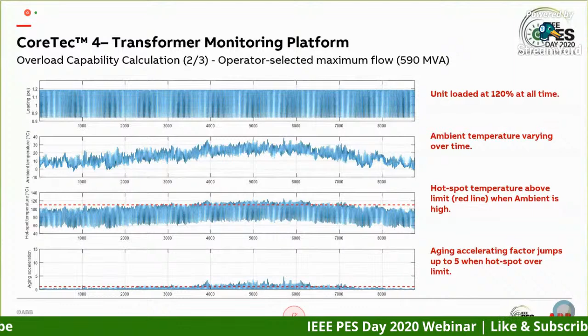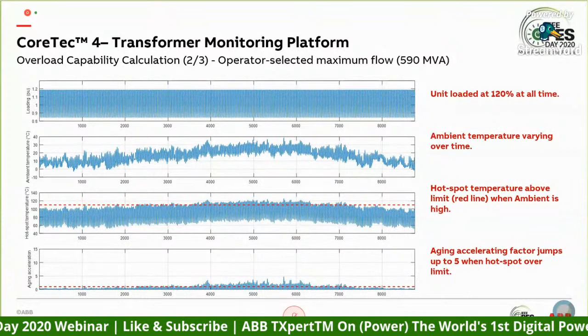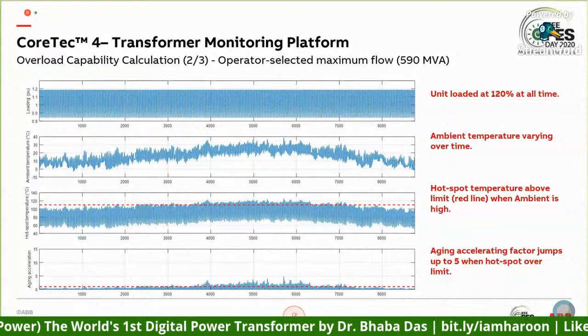In some durations, you can see the hotspot temperature is above 110 degrees for a certain period of time. And when that happens, your aging acceleration factor jumps from 1 to 5 when the hotspot is above the limit. This is something we don't want.